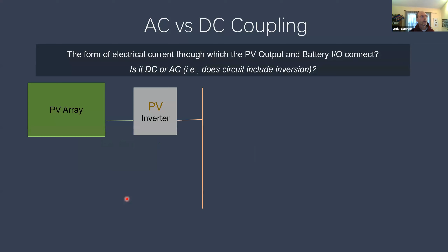What we see is a PV array going to a PV inverter, which has its AC and DC components, and then we might have a PV array going to a hybrid inverter. Now, this hybrid inverter is an inverter that can also take a battery input. And the point here is that this hybrid inverter setup on the right side is future looking. It's saying, I think I'm going to get a battery someday. If I want to get a battery for the left side, I have to add a battery inverter. So that's a second inverter.